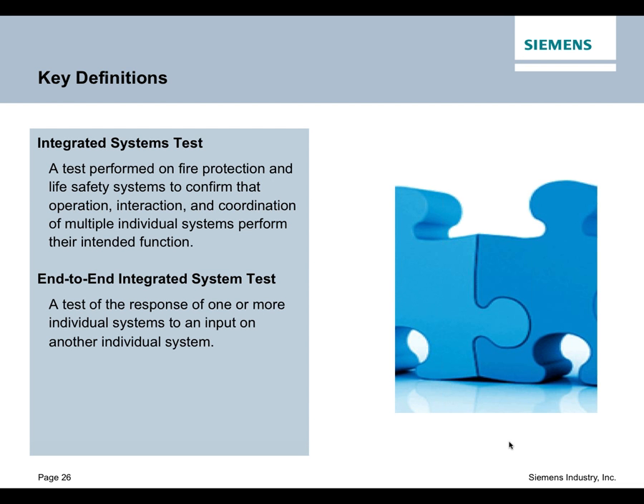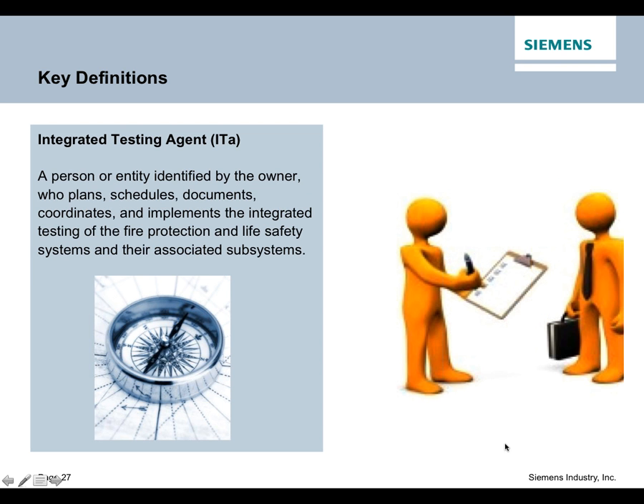You'll see that there are key definitions in there for the integrated systems test, the end-to-end integrated test. Once again, it's just helping to define what this means. I always like to use that end-to-end concept because that's letting us know that I'm testing that smoke detector in the elevator lobby, watching it go through the control panel, watching it actually recall the elevators to make sure that these things are actually happening.